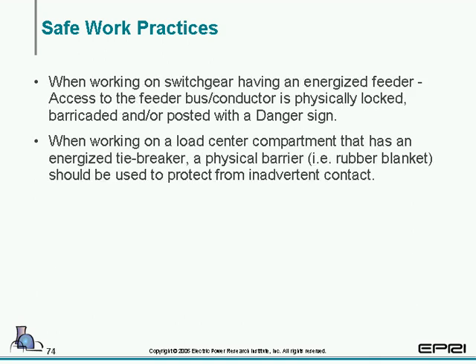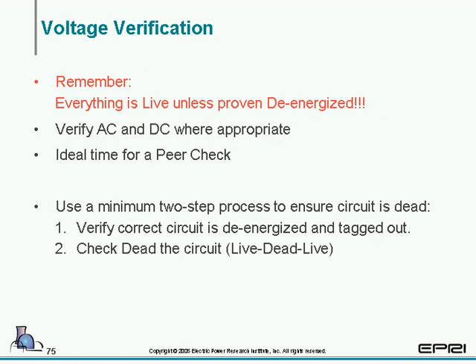And we're going to talk about flash protection boundary here in a little bit. Continuing on with safe work practices. Access, if working on an energized switchgear with an energized feeder, access to the feeder or bus conductor is physically locked, barricaded. I think we already went over that. Use of physical barriers such as rubber blankets can be used. Remember, everything is live unless proven de-energized.